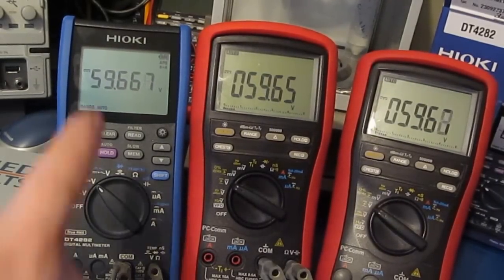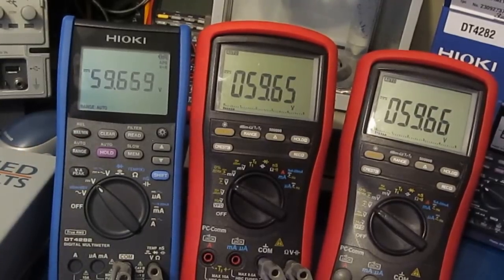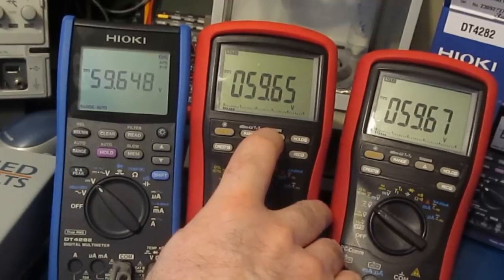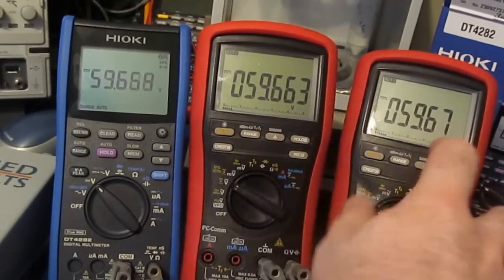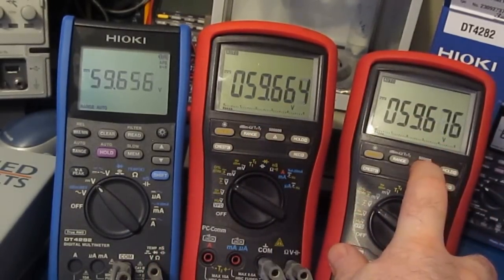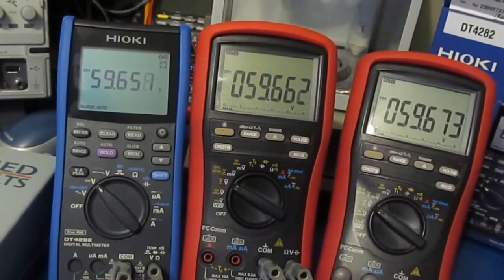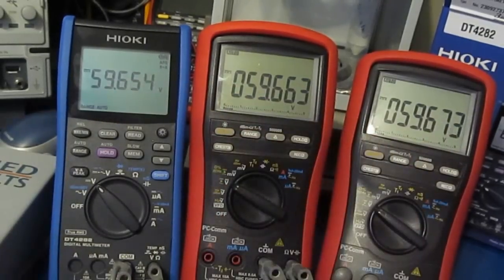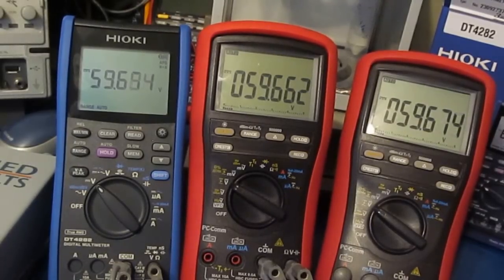Here you can see this meter is a 60,000 count meter. If we want more resolution in DC volt mode, we can select the 600,000 count mode and gain that extra digit if we need it. Again, people talk about the instability of this mode, but you can see that's not really an issue. All 3 meters are basically reading the same value.